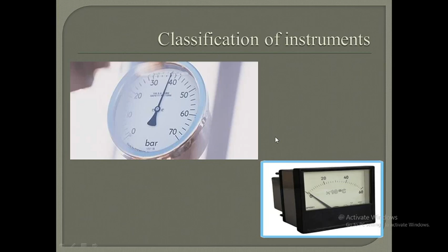The next classification of instrument is absolute instrument. These instruments give the magnitude of the quantity under measurement in terms of the physical constant of the instrument, such as the tangent galvanometer, which is used for calibration of measuring instruments manufactured by different manufacturers. These instruments do not require comparison with any standard instrument. They are used by national laboratories, and working with absolute instruments for routine work is very time consuming, requiring a lot of adjustments.